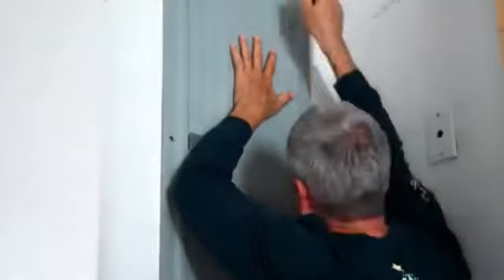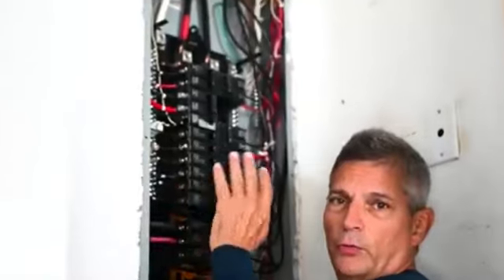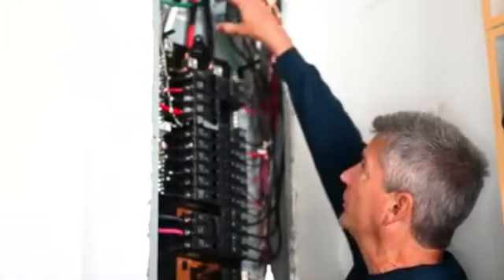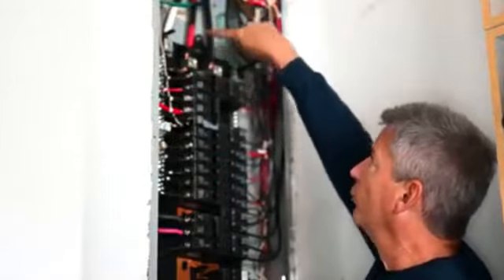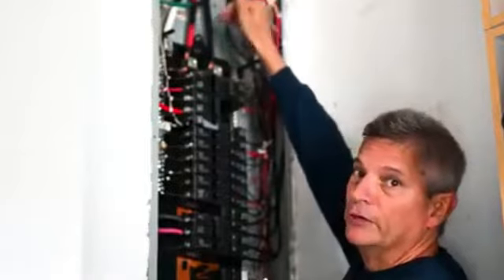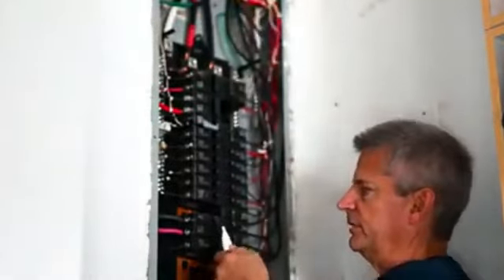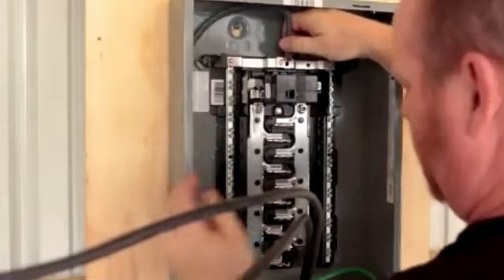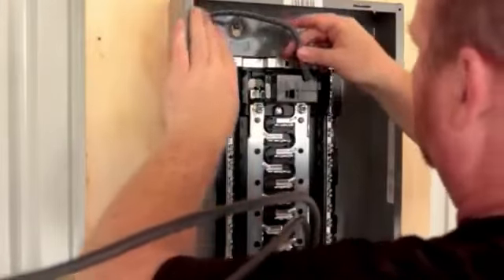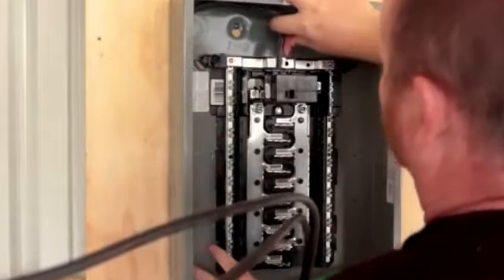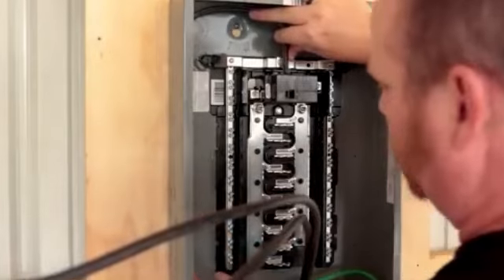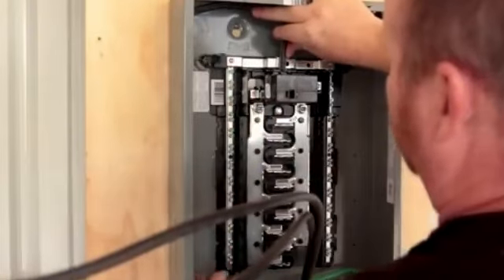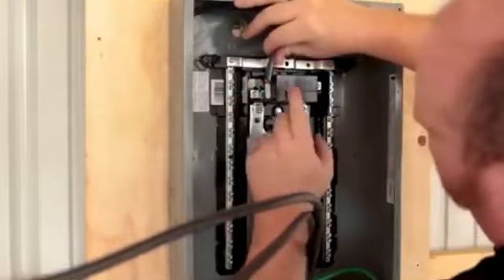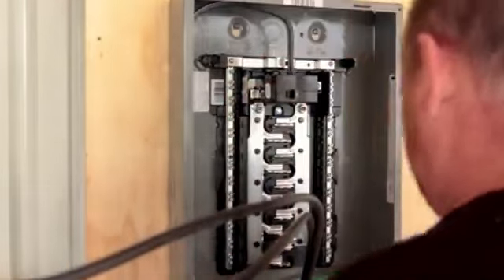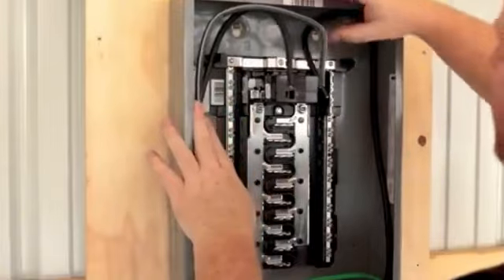4. If your house was built between 1965 and 1973, hire a licensed electrician to verify your branch circuit wiring type. Pull 3 outlets in different rooms and check the cable. If aluminum is present, retrofit every outlet, switch, and junction box with Alumiconn or Copalum connectors. Cost $1,050 to $2,100 for a typical 35 connection home. 5. If your main panel is 100 amps and you have added major electrical loads in the past decade, upgrade to 200 amp service. The work requires utility coordination and a service drop replacement, but it eliminates chronic overload. Cost $3,000 to $5,000 depending on service entrance configuration. Total cost if all 5 issues exist, under $6,000. One electrical fire averages $47,000 in damage.